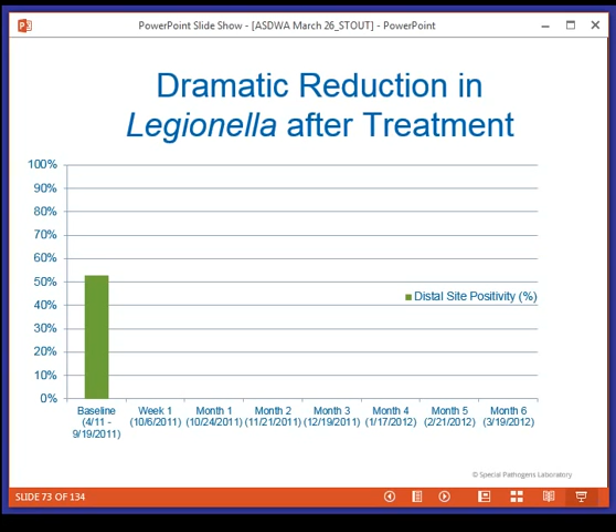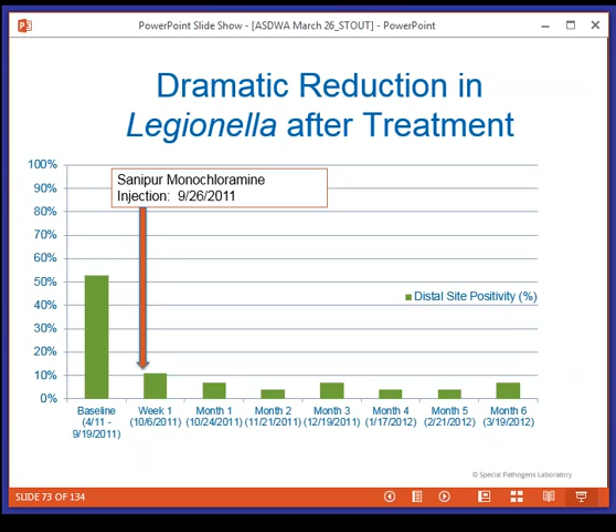Two things about this graph: one is dramatic reduction, the second is it's not zero. It's almost zero, but not quite. So what did we learn? You're injecting at about 1.5 to 3 parts per million. The benefits are fewer disinfection byproducts than chlorine, on-site generation, and you can apply it to hot water where the organism lives. So now we've proven it's effective in reducing Legionella positivity.